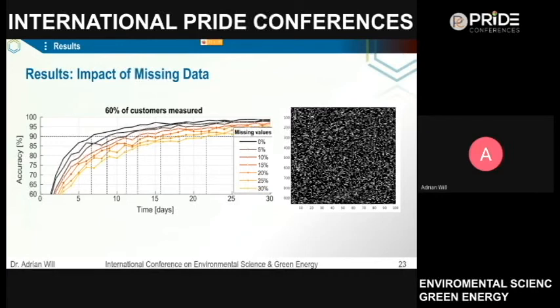It's not magic, it's just good science. Working with the original Pearson correlation coefficient gives an ugly result, but working with the first difference between the next measure and the first really separates the measurements and gets this result. So you have a wide difference between the correct phase in derivative and the two incorrect phases in derivative, and that wide difference is what makes it resilient, resistant to missing data. Anyway, you fill out these gaps and you will still get the correct result because the difference is too wide. So it solves the problem quite well, even in the presence of missing data.